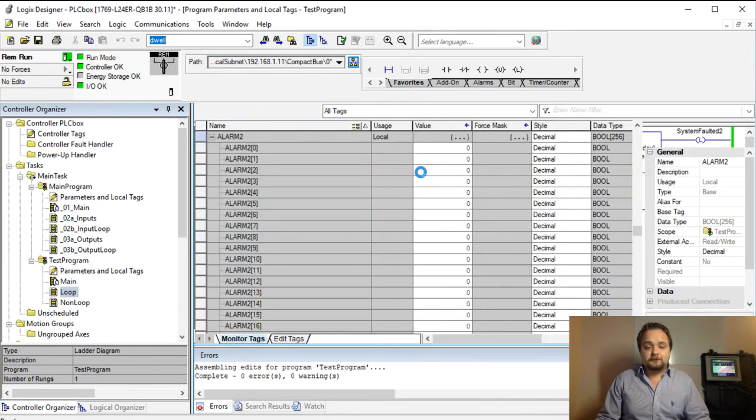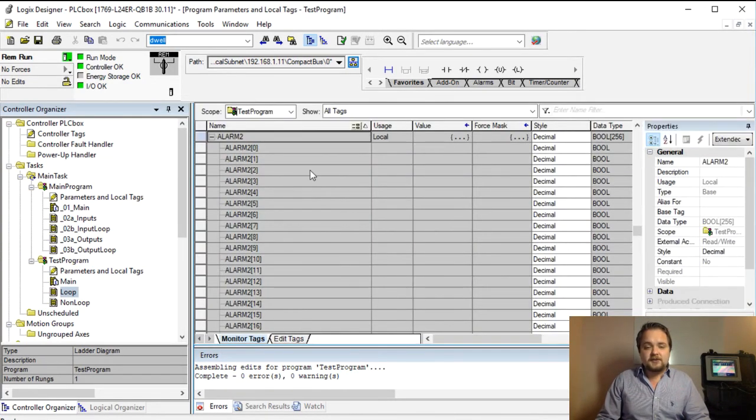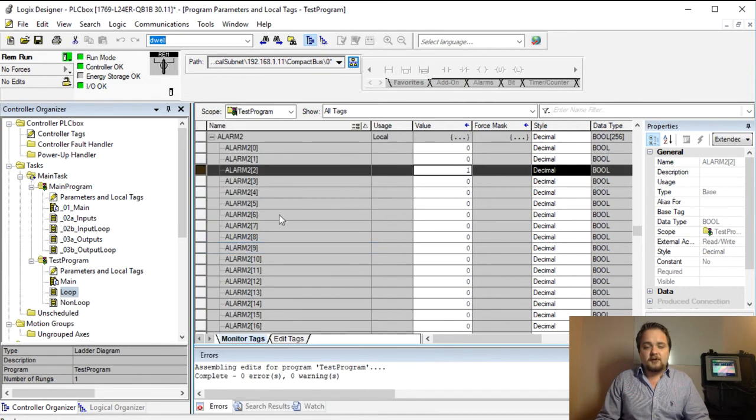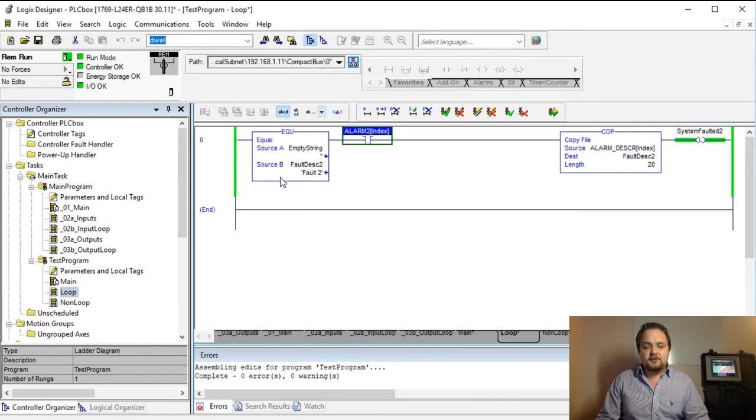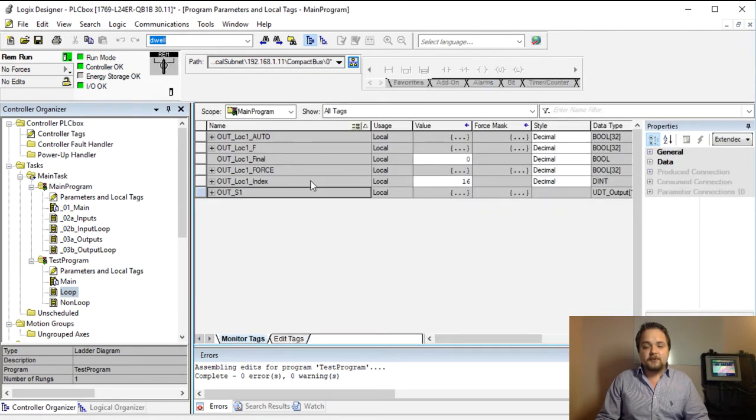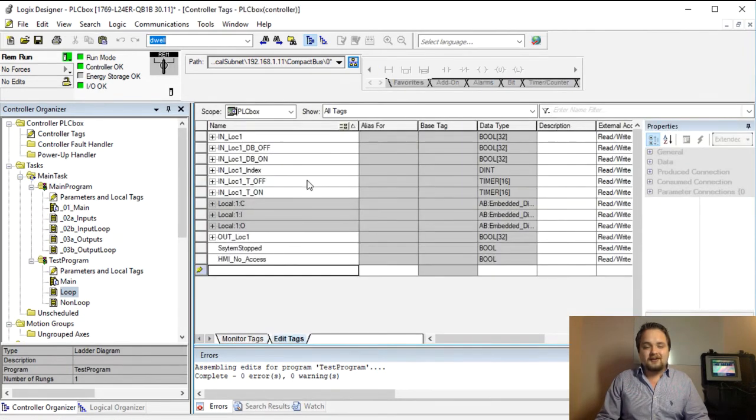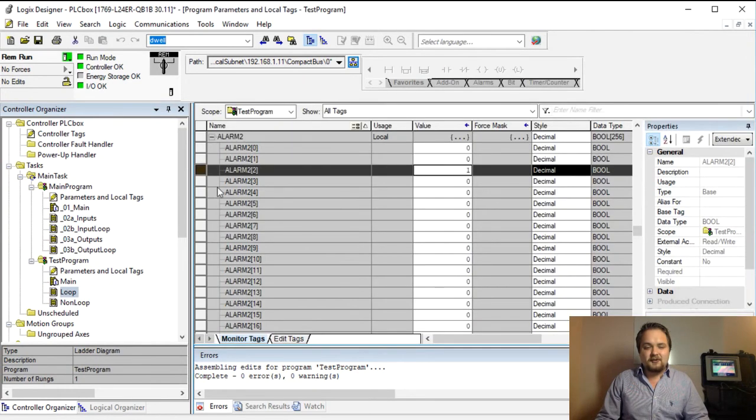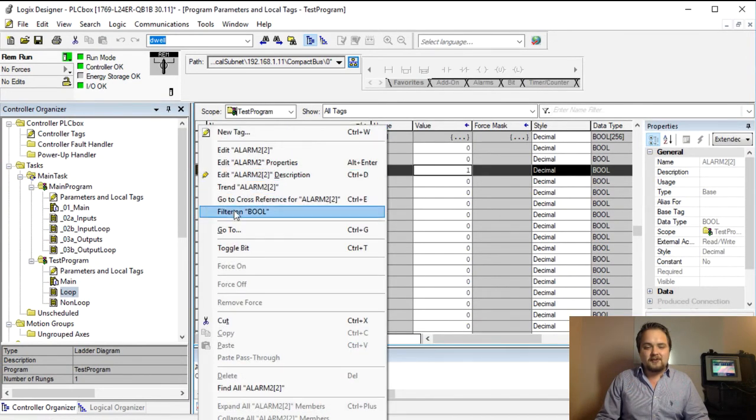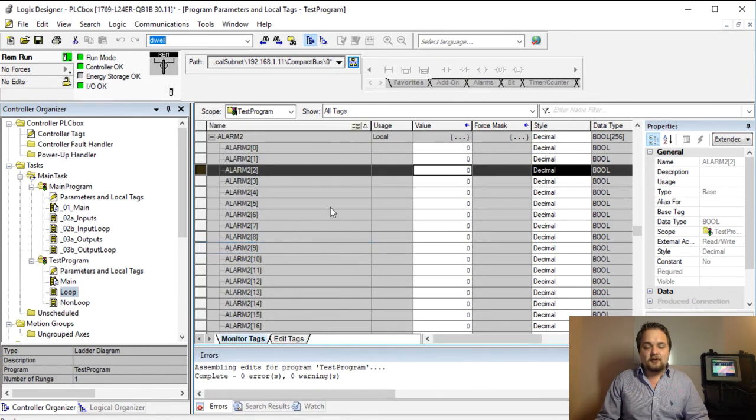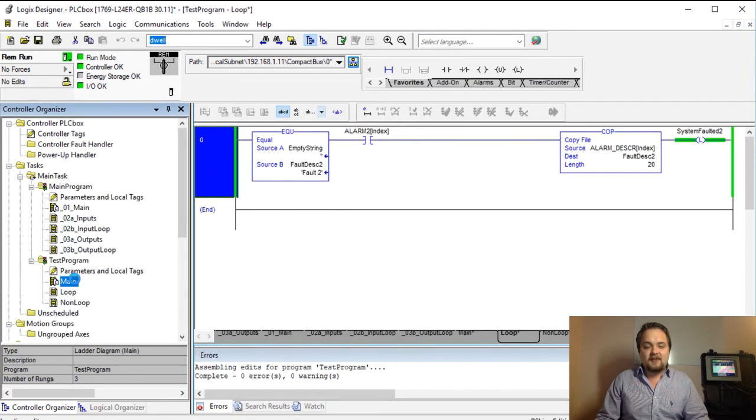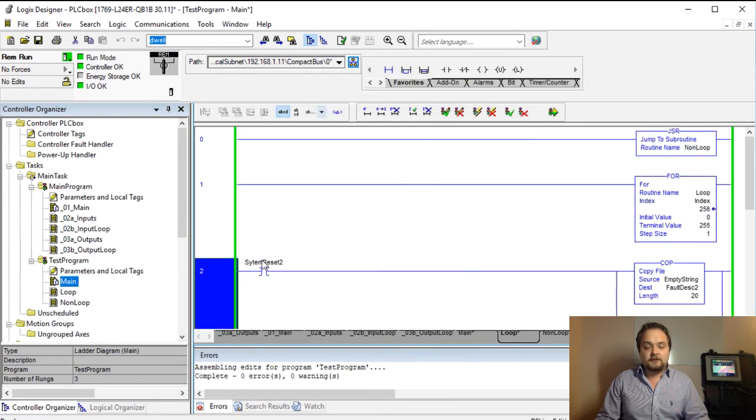One thing to notice is that it's difficult to toggle these bits through this particular rung of logic which is perhaps the drawback of this particular implementation so what we need to do here is essentially go into this alarm two and number two and for example if we're going to toggle this bit we have alarm number two which has occurred and you will notice that our system has faulted and the fault description is going to be fault number two now I can clear this I'm just tabbing through the many windows that I have open so I can clear this back to zero and at this point I can reset the system back from my main routine.